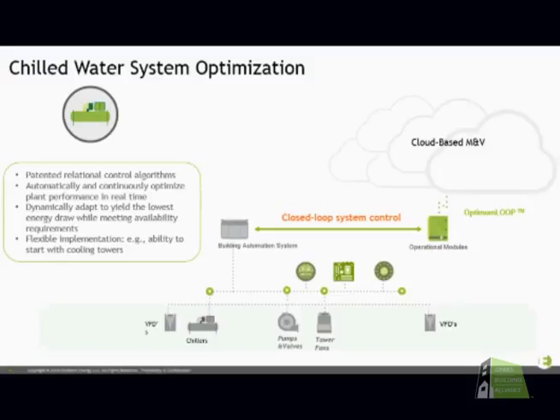If you have an optimized plant, what you'll typically have is a closed-loop system with an additional module that resides on top of the building automation system and is dedicated to just looking at what is the energy that I'm putting in for the amount of cooling that I'm getting out, and how can I respond to that, again, looking at the entire system, not just looking at individual components.